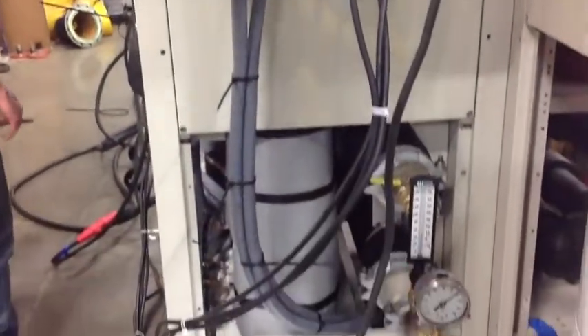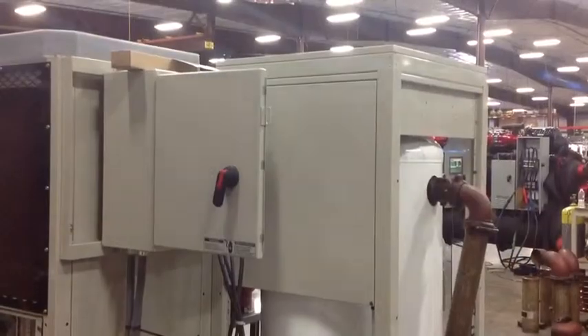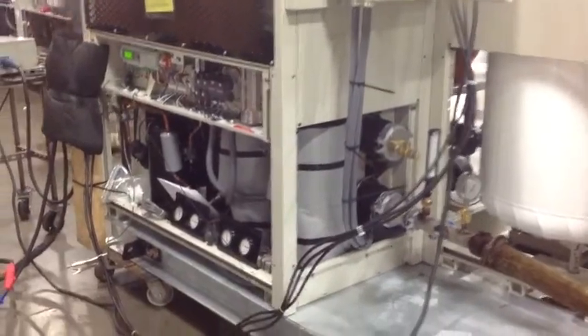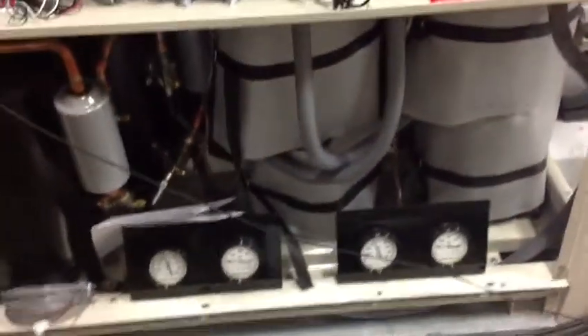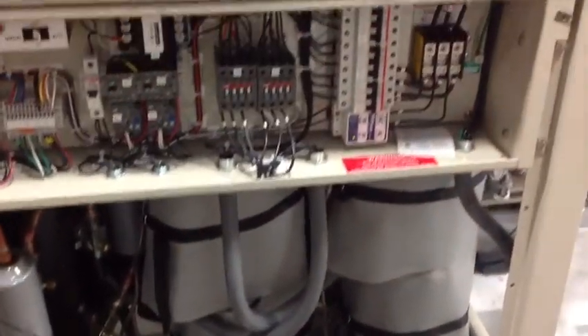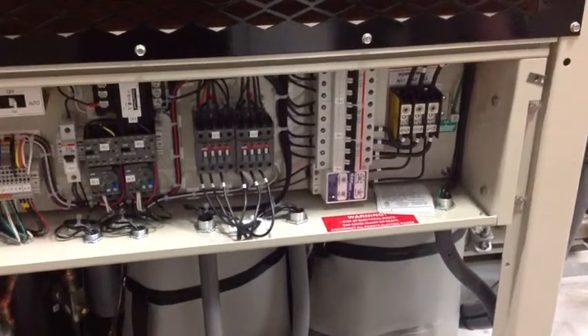We'll pan down to see the leaving connection, which is on the bottom of these 2 headers. The top header is the entering connection into the mechanical module. Pan down and across, you can see in the foreground the 2 scroll compressors. This module has independent circuits, so there are 2 sets of suction and discharge pressure gauges on the bottom.